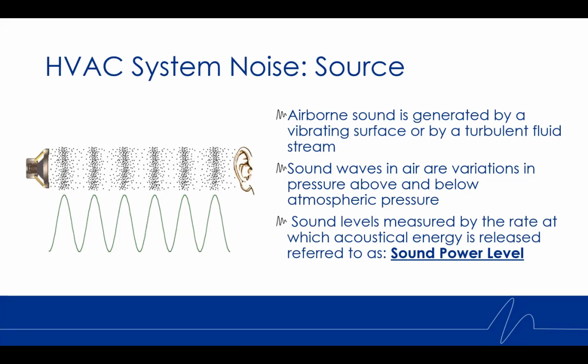So let's talk about HVAC system noise. Let's look at the source here. Airborne noise is generated either by a vibrating surface or a turbulent fluid stream. In the case of HVAC noise control, it's essentially going to be when you have a fan. That fan is going to disturb those air particles, and it's going to create concentrations of air particles below and above atmospheric pressure. That's the image on the left there. We have a lot of air particles that are condensed, and then they expand and condense and expand. And that's the sound wave. That's how the sound travels through the air. That's how it propagates itself. Typically, we express those concentrations of air in that wave that you see right below it.